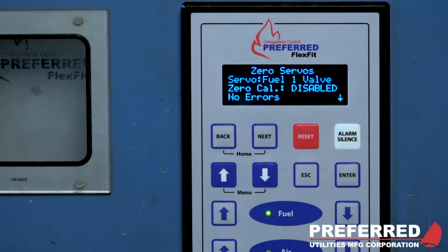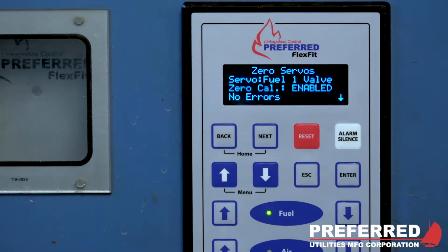Now scroll down to zero calibration. And what you will want to do is choose which servo you want. So in this case, we're going to do fuel 1 servo. Go down to zero calibration, press enter, and now it's enabled. And then we will go to the servo and perform the calibration.